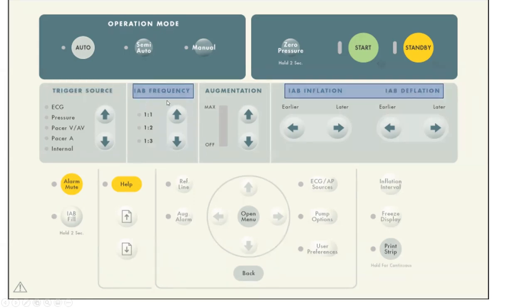And this is how on that console you can manipulate the frequency. You can go from 1 to 1, to 1 to 2, 1 to 3. And you can adjust the timing of inflation if you don't like it. If you think the balloon is inflating too early or too late, you can make adjustment. And I will explain those a little later. But to make those adjustments, usually when you connect the balloon pump, you click on start and it will be on auto mode. If you want to make adjustments, you have to click semi-auto mode and click start again. If you click semi-auto mode, the balloon pump just stops inflating. So you click semi-auto mode, you click start, then you go 1 to 2, 1 to 3, or you make adjustment to the inflation deflation timing.